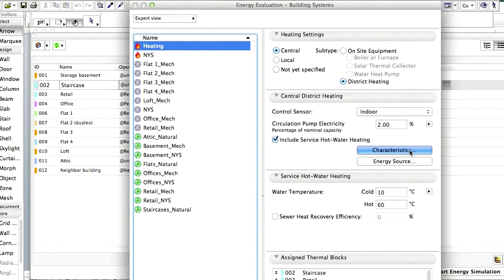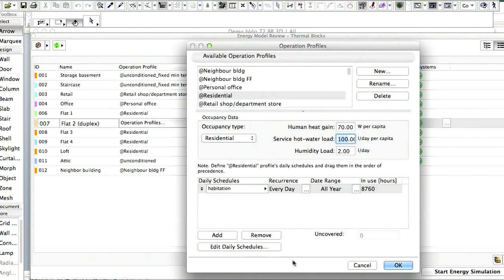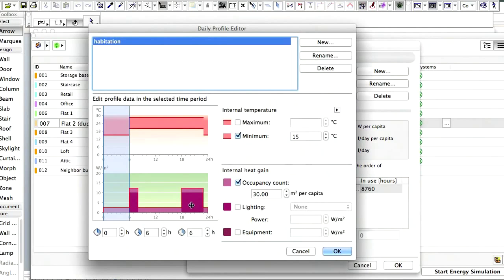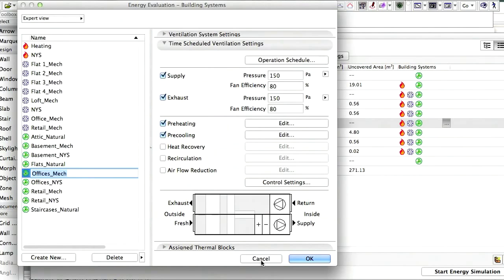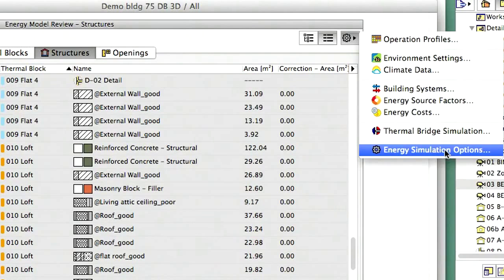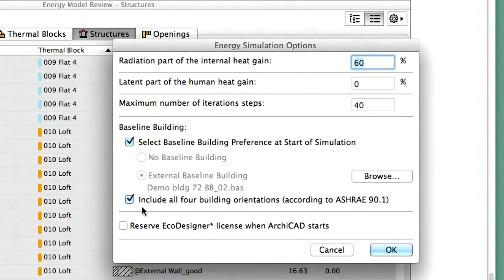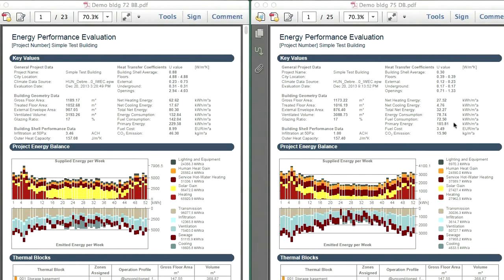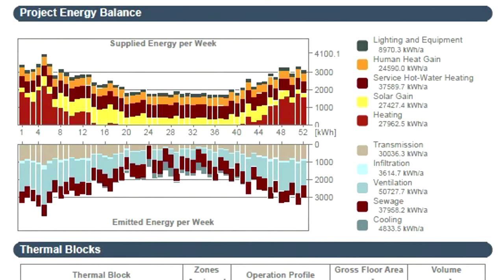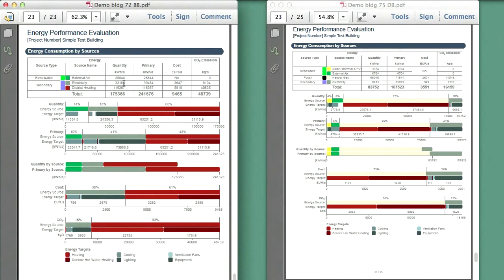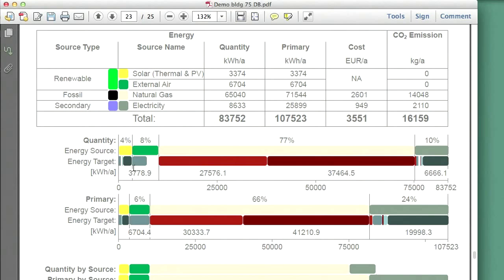The Building System Efficiency Optimization video clip presents how to test different building system strategies to define the optimal low-energy building solution set for the design project and how to evaluate overall building energy efficiency with building systems included. The energy simulation is run in the Building Energy Performance Rating mode to produce results that enable a quick and effective comparison of the designed building's energy performance with the baseline building's energy performance. In addition to the Building Energy Performance Rating, fuel consumption, fuel cost, carbon dioxide equivalent emissions and primary energy calculations are also executed at this final stage of the energy-efficient building design.